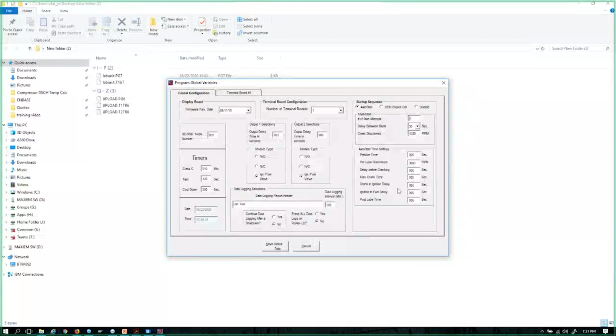Now remember, the DE-3000 power supply board has 4 primary output modules, numbered 1 through 4. When we talk about prelube time, prelube is always linked to output module 4. So it counts down backwards. In the startup sequencing, if we wanted a prelube, here's where we would tell it our prelube time. Let's use an older 6 1/4 bore Cat, like a 379 Caterpillar engine, maybe with a CPU 95 ignition system on it. We'll say we want to prelube the compressor and engine, or maybe just the engine, for a total of 60 seconds. And then we want to disconnect the prelube when we sense a certain RPM, maybe something as low as 100 RPMs.